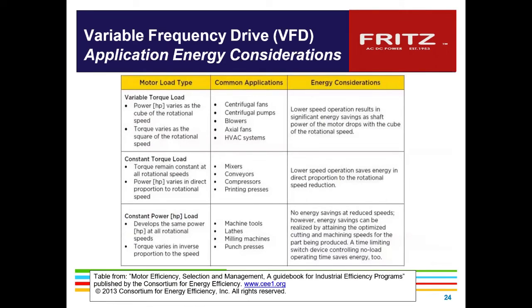So, variable frequency drive applications for consideration: the horsepower varies with the cube. Your torque is the square of the rotational speed, and these are all pieces of the application. And if you can control the lower speed, then you get the power reduction.